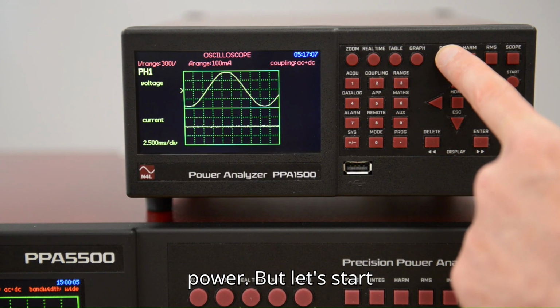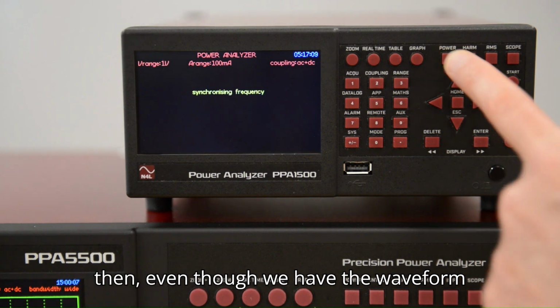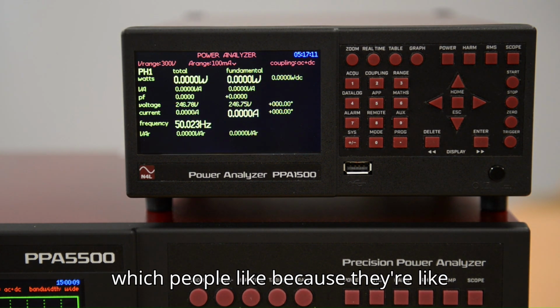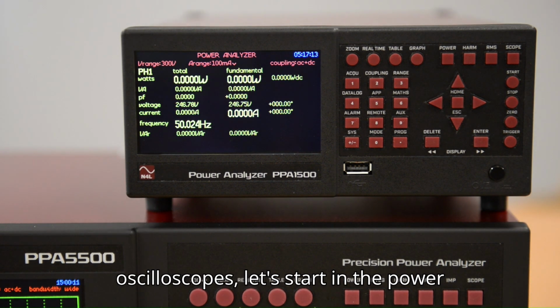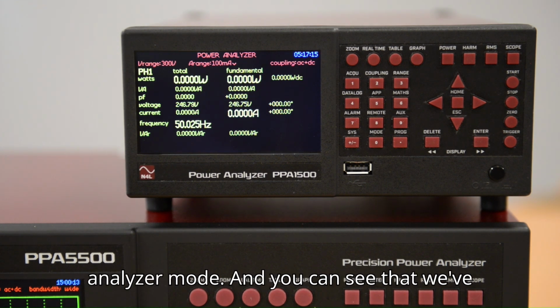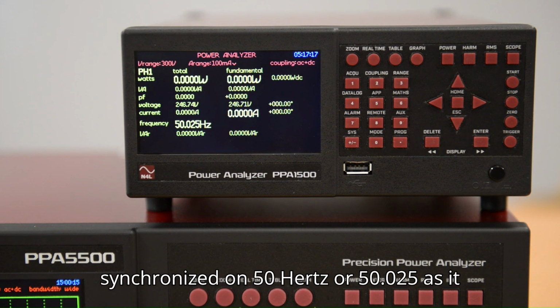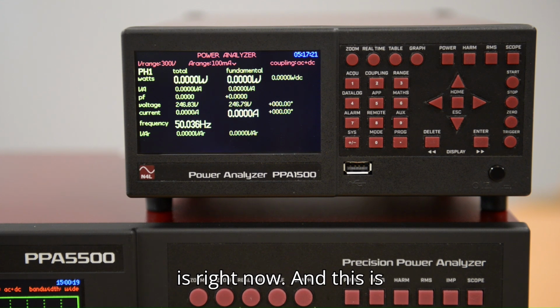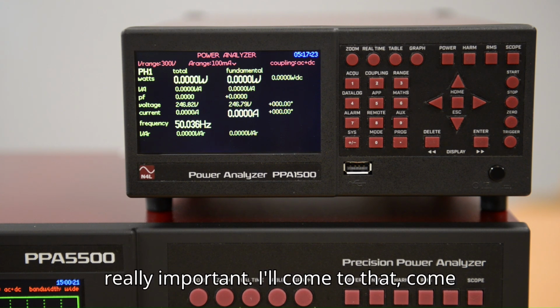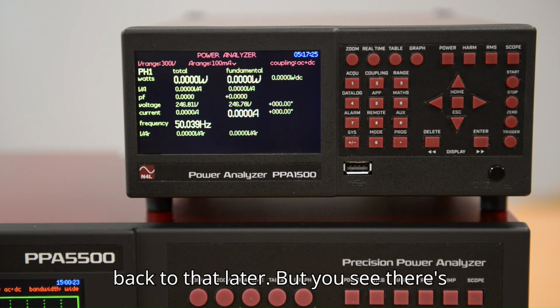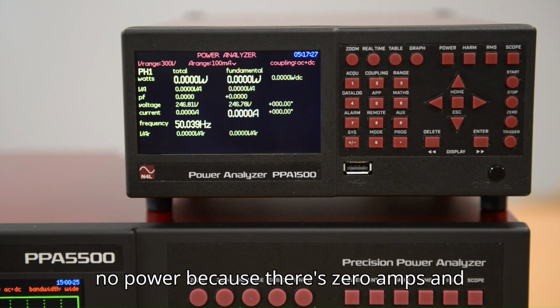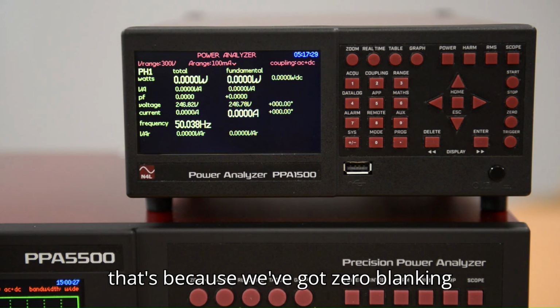But let's start then. Even though we have the waveform, which people like because they're like oscilloscopes, let's start in the power analyzer mode, and you can see that we've synchronized on 50 Hertz, or 50.025 as it is right now. And this is really important. I'll come back to that later. But you see there's no power because there's 0 amps. And that's because we've got zero blanking enabled.